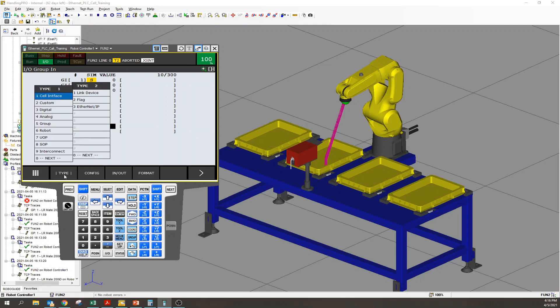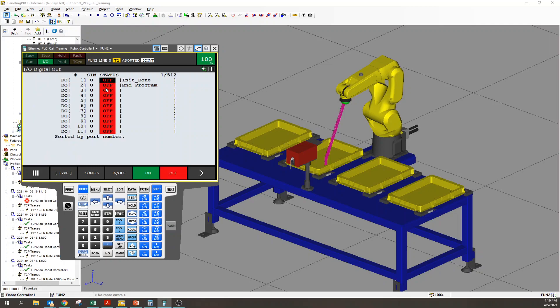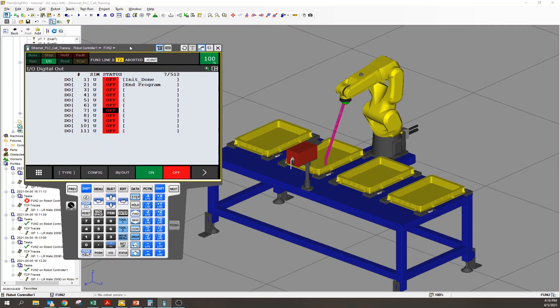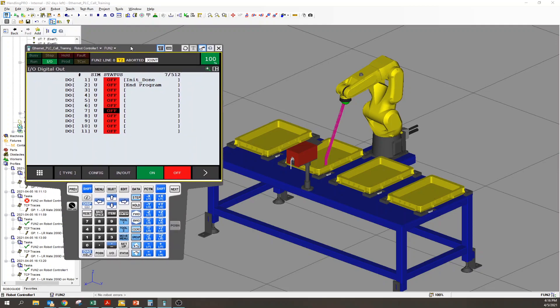So when we say group I/O, think of having a bank of ones and zeros that are either on status or off status, and we're going to convert that into a number that the robot can use. That's because most of your ethernet comms - your profibus, profinet, Modbus TCP - all of those options give you thousands of discrete I/O, but they don't give you floating point integers. I want to show you how to work around that and some tips and tricks for setting up your robot to do that.